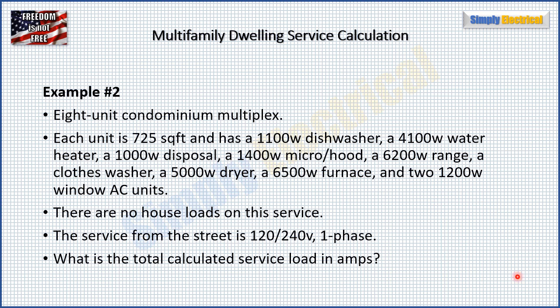Example number two: we have an eight-unit condo. Each unit is 725 square feet, has a 1,100 watt dishwasher, 4,100 watt water heater, 1,000 watt disposal, 1,400 watt micro hood, 6,200 watt range, a 5,000 watt dryer, 6,500 watt furnace, and two 1,200 watt window AC units. No house loads, 120/240 volt single phase service. What is the total calculated service load in amps?